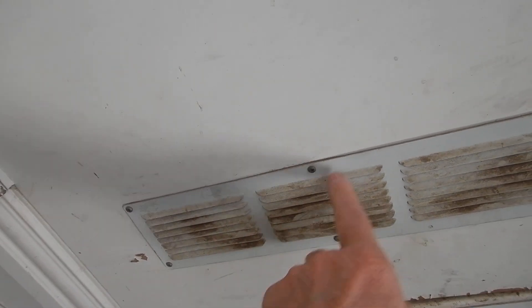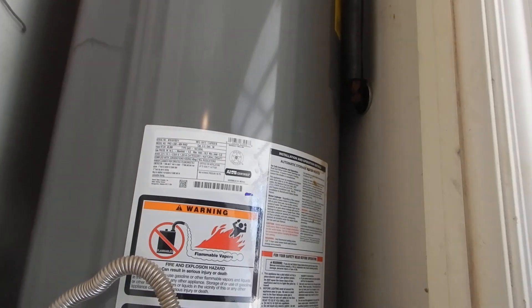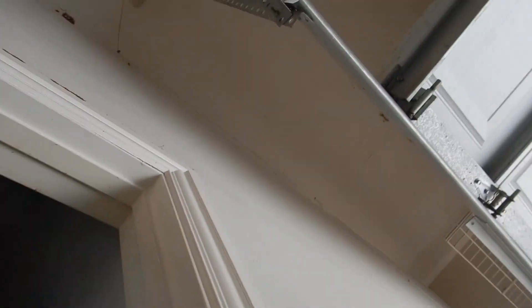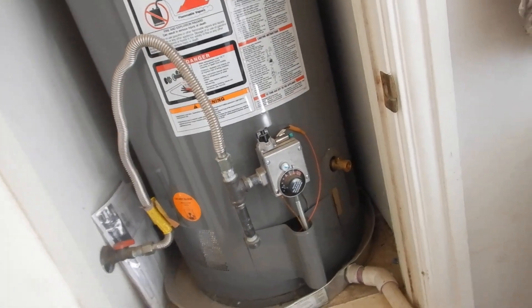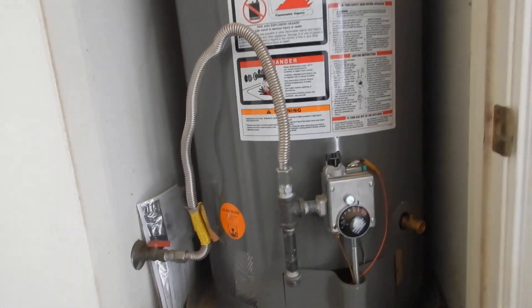This is our combustible air vent — see the dust on that? That air comes in and it feeds the water heater flames. I am not seeing any makeup air in this closet. I cannot determine how this water heater gets the makeup air — you're burning air, so that means it's getting depleted. When you have a closet like this, the air is supposed to be made up for. Oh! Right there on the same door — air intake and makeup air. Never mind, let's just keep going.